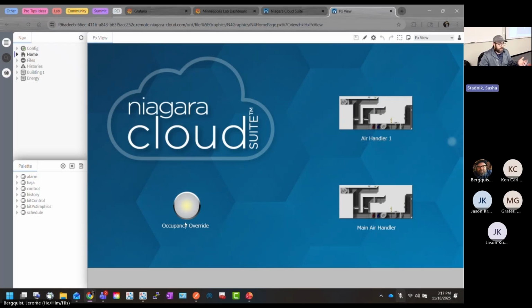So that's there now. That's another reason you're not going to need to be running a machine with Workbench licensed. You can connect remotely. If you have a customer that has an install tech that goes and installs a VAV into a site, and it's all just BACnet points, a BACnet device and BACnet points, you don't need to go out there.